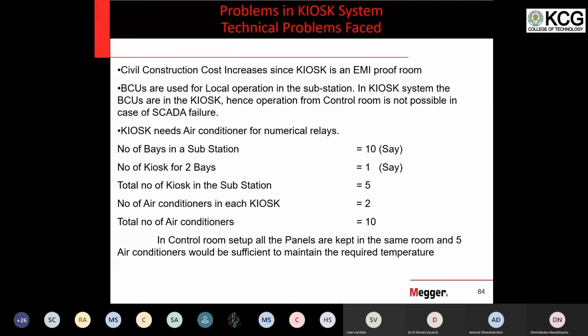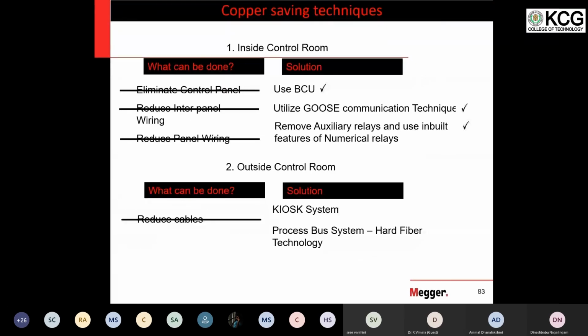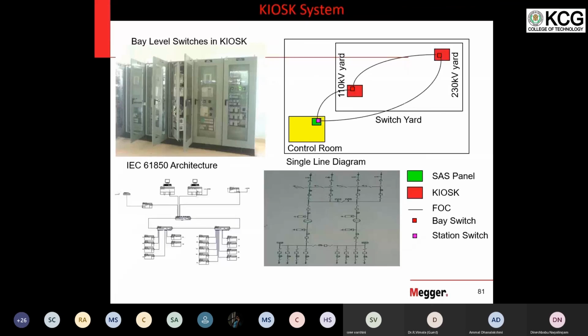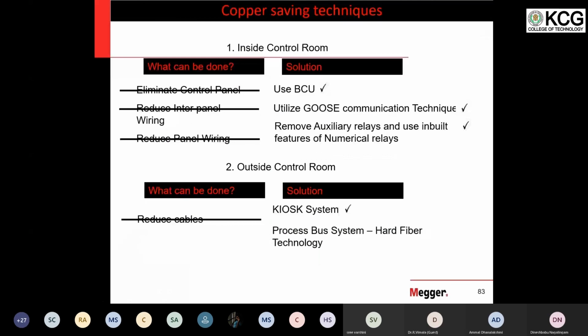So what we mean here is, we eliminated the control panel and we kept something like this called the bay control unit. So in this BCU, you can press buttons and operate the system. But what we did here, this entire panel is kept in the switchyard and the operator is sitting in the control room. So a computer can fail anytime. If the computer fails, next is local operation. He has to operate from the relay. But where is the relay? Relay is kept in the switchyard. This is the biggest challenge. So earlier we said that BCU is for local operation, but now that is removed from the operator.